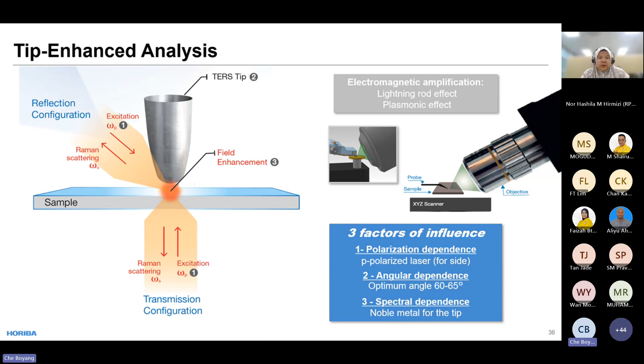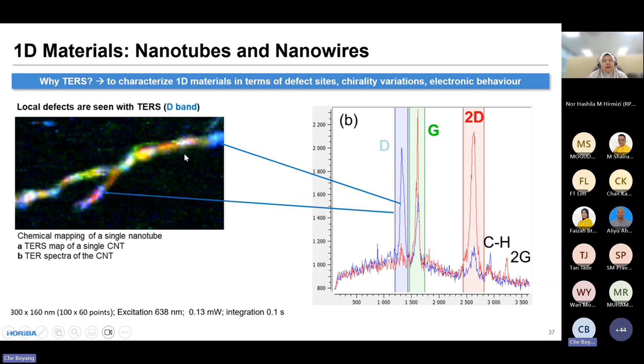So this is the example to show this kind of capability. If you are using the nano Raman, we are able to scan very small size samples. For example, this is a carbon nanotube. We'll scan AFM first to get the morphology of this tube. So this is a single tube, and then we can do the Raman mapping. And the mapping will be exactly the same resolution as the AFM. So we are able to get the nanometer resolution here. In this case, we're studying the DG band, so we can get a little bit of information about the defect of your carbon nanotube along this single tube here.